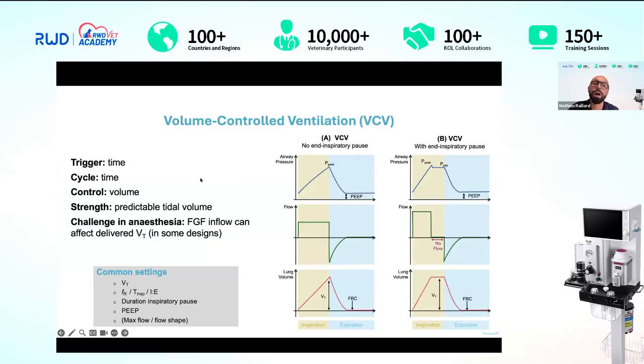So what happens over time? My flow in volume control ventilation is a square wave and is continuous throughout. Pressures increase as the gas is going in the lung and stays in the lung, and at the end of the inspiration, I have my tidal volume. So what do I set when I set a volume control ventilation? I set my tidal volume. Generally, most people will start with 10 milliliters per kilogram of tidal volume. I set my respiratory rate and either, depending on the ventilators, my inspiratory time or the ratio between inspiration and expiration, which will give me the inspiratory time.